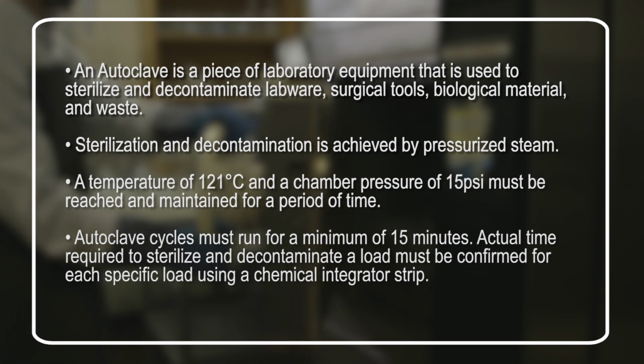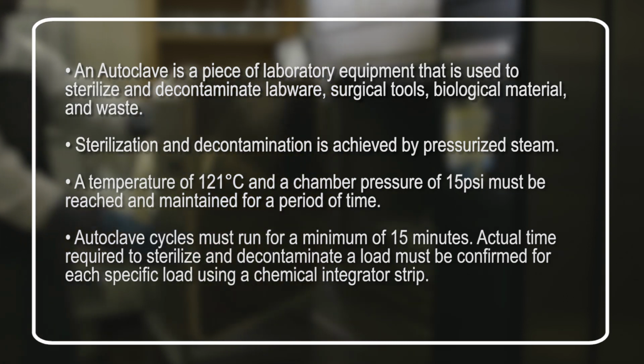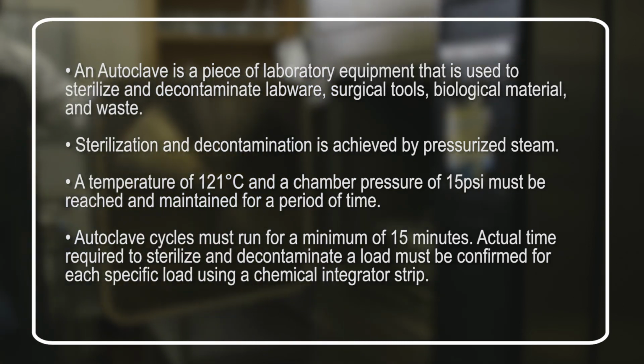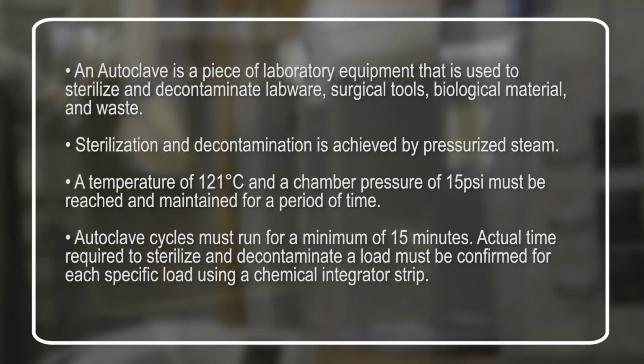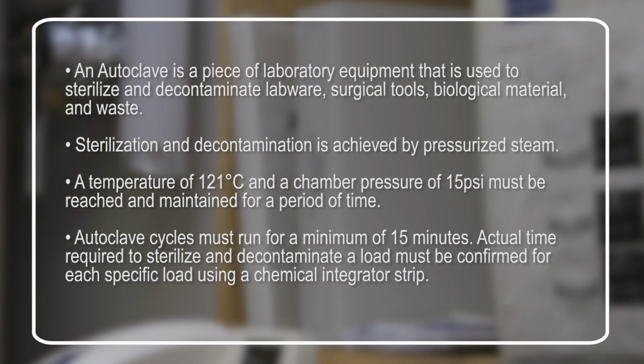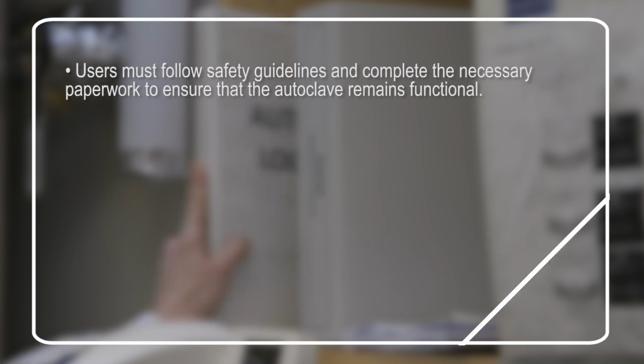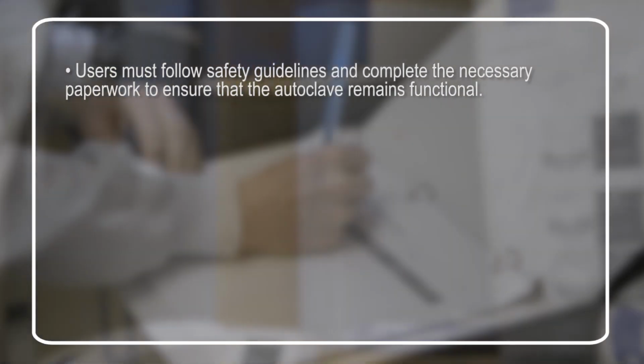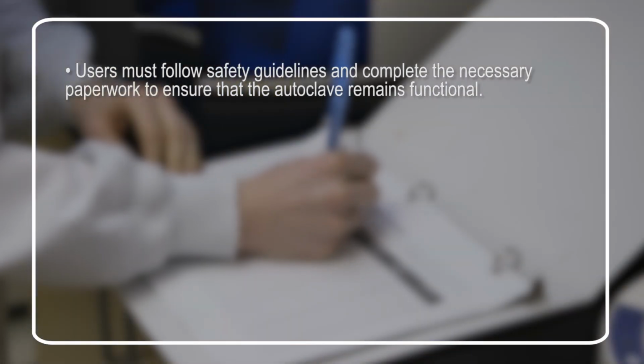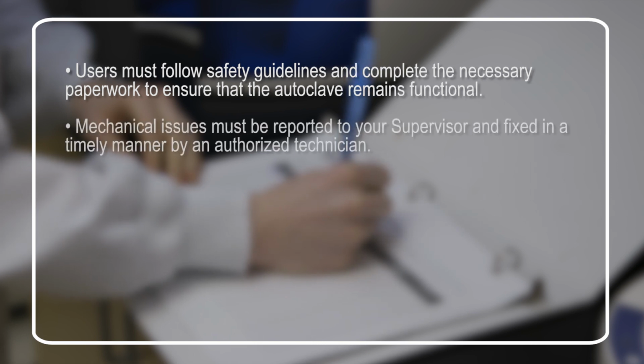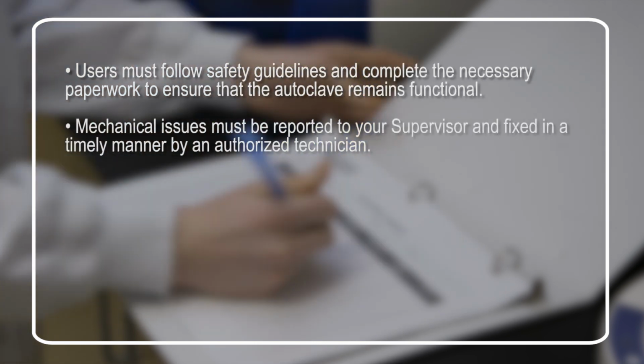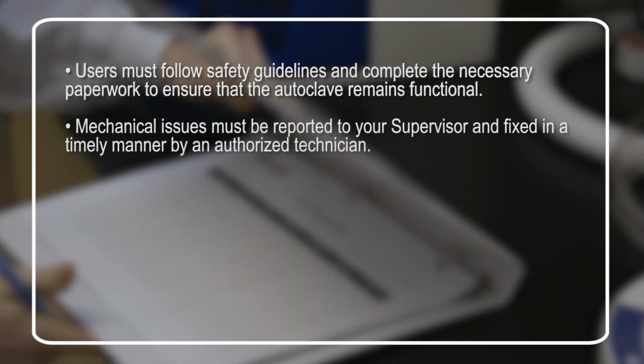Autoclave cycles must run for a minimum of 15 minutes, but the actual time required to sterilize and decontaminate a load must be confirmed for each specific run using a chemical integrator strip. Users must follow safety guidelines and complete the necessary paperwork to ensure that the autoclave remains functional. Mechanical issues must be reported to your supervisor and fixed in a timely manner by an authorized technician.